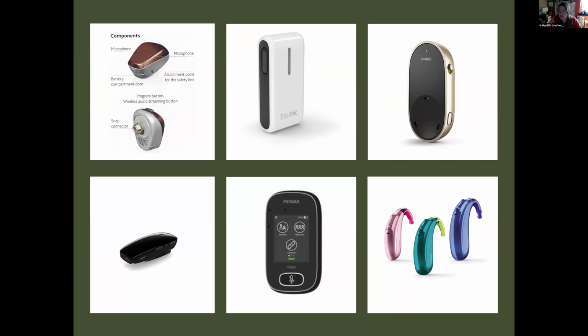First, I want to start with BAHAs because this is one that I see the most issues with in regards to connecting to the remote microphone. So top left, you have your BAHA device. If it's an Oticon, you're going to be connecting to something kind of like the Connect Clip, which is on the bottom left. Once they're paired together, which is, it goes into automatic pairing mode when you turn it on. And once you turn on the BAHA, it should connect once they're close together. However, that does not mean that the BAHA is in the remote microphone mode. They're just connected. To get to the remote microphone mode, on that picture of the BAHA, there's a button that says program button. You have to press and hold that button that's on the top of the BAHA for 3 seconds. And I'm talking 1 Mississippi, 2 Mississippi, 3 Mississippi, and release, and you'll hear a da-da-da-da.